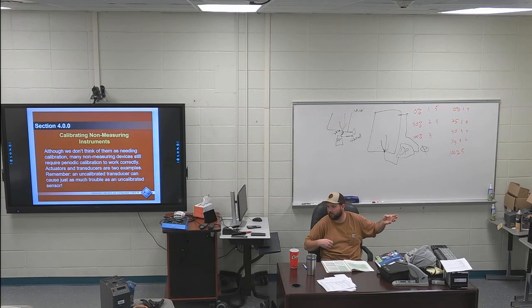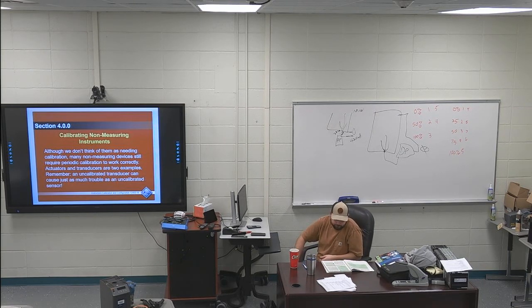You have all different kinds. That's by far the most common. You can have voltage to pressure, pressure to voltage, anything like P to I is very common. Like the pressure transducer that's on the bottom of the tank, that's taking a pressure in and outputting a current, right? But I to P, current to pressure, is the most common type. The word transducer literally means to change from one form of energy to another.